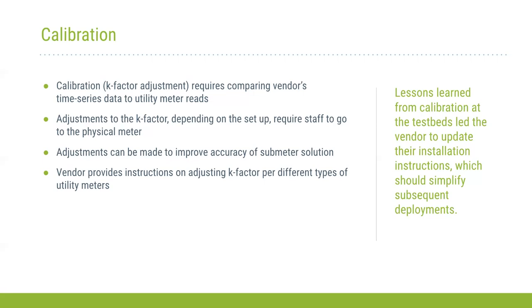Now, you can adjust the K factor. In some cases with GSA here, it did require the staff to physically go to the meter. However, the vendor does offer different options to avoid that issue, which was part of some of the focus group results, which Joshua can get into. The adjustments can be made to improve the accuracy, and once we narrowed it in, data started flowing, and we didn't need to calibrate anything else. I do want to mention that with multiple types of utility meters, the vendor does offer instructions on adjusting these K factors and on installation, and they were very helpful throughout this process. We did find that there was slight confusion in the instructions, and the vendor actually adjusted them to make it a more simple and easy process. So yeah, that was nice of them to do that. Next slide, please.